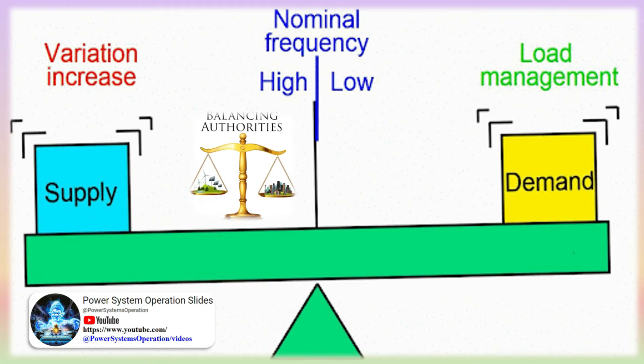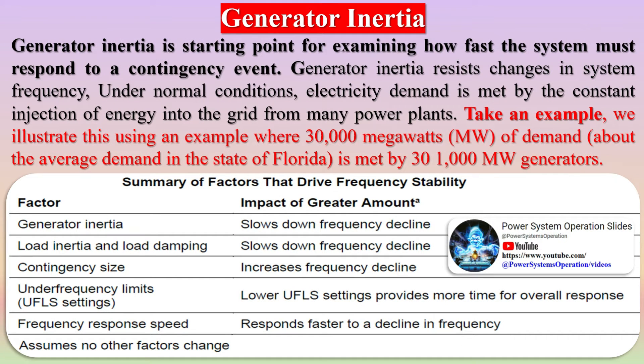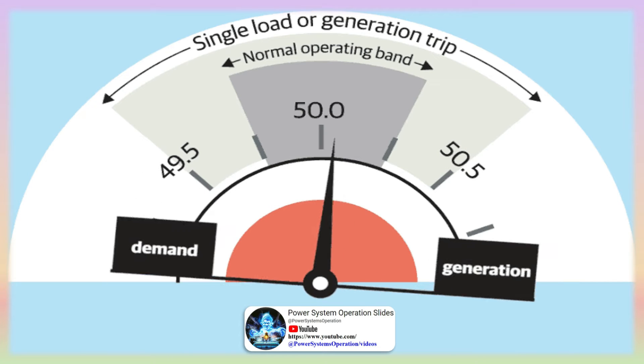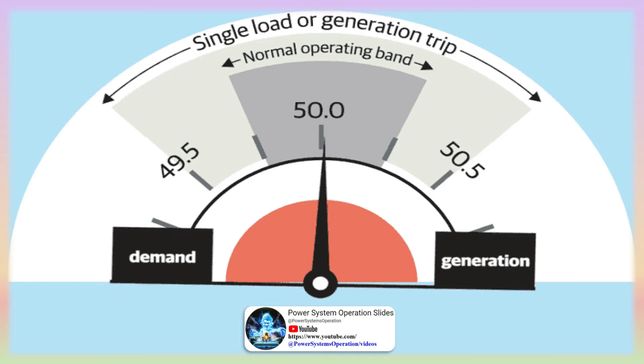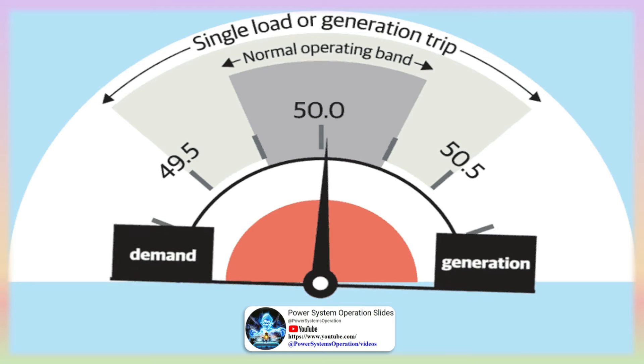Generator inertia is the starting point for examining how fast the system must respond to a contingency event. Generator inertia resists changes in system frequency. Under normal conditions, electricity demand is met by the constant injection of energy into the grid from many power plants. For example, 30,000 MW of demand — about the average demand in the state of Florida — is met by 30 1,000 MW generators. If one of these generators were to fail, the remaining generators online would only provide 29,000 MW, but loads would still extract 30,000 MW.